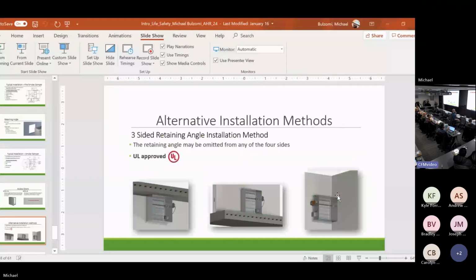Access doors, 3-sided installation. So our retaining angles are typically 4-sided. They could be on one side of the damper or both. There's size limitations on where you can use them. But every once in a while, I'm in a jam. My damper is tight to the floor, tight to the wall, tight to the ceiling, and I don't have the room to install one leg of my angle.